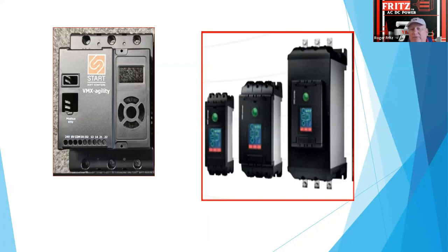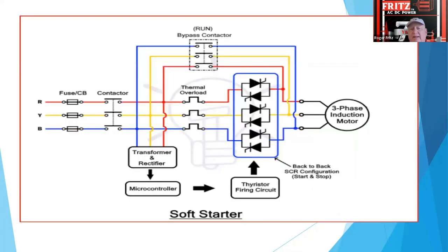Then they came out with a little bit more advanced type that has what they call soft start and soft run. When the motor is not fully loaded, you really don't need to be giving it a full 100% voltage. So this device stays connected, keeps the SCRs in. It automatically watches the current, voltage, and torque of the motor, and it regulates that power.